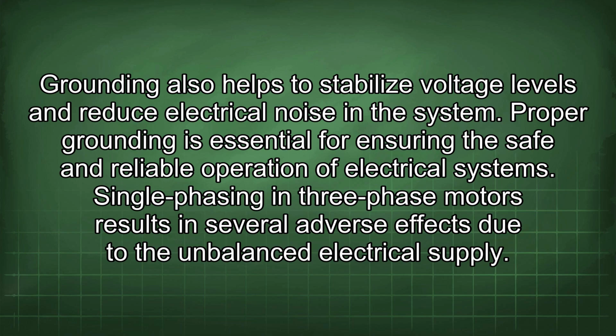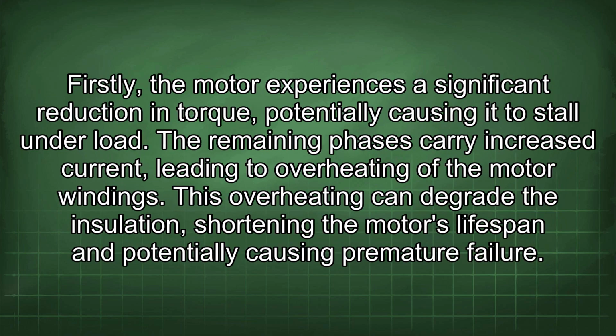Single-phasing in three-phase motors results in several adverse effects due to the unbalanced electrical supply. Firstly, the motor experiences a significant reduction in torque, potentially causing it to stall under load. The remaining phases carry increased current, leading to overheating of the motor windings. This overheating can degrade the insulation, shortening the motor's lifespan and potentially causing premature failure.